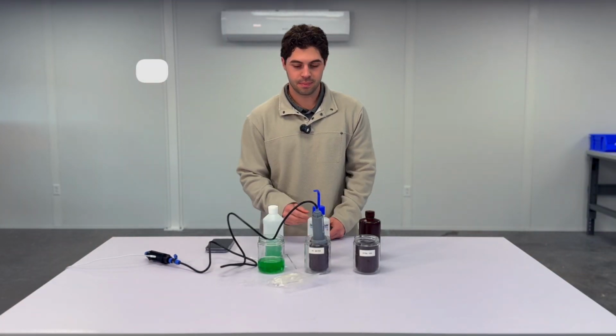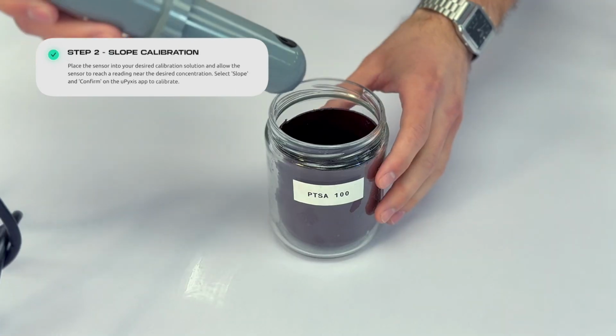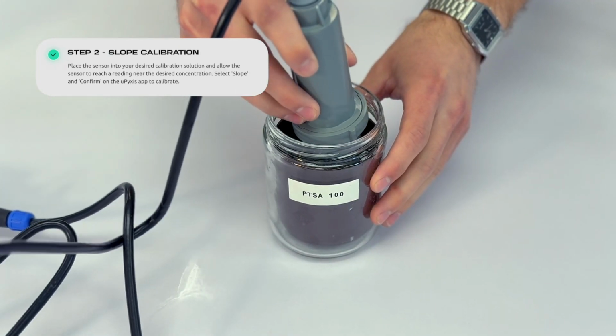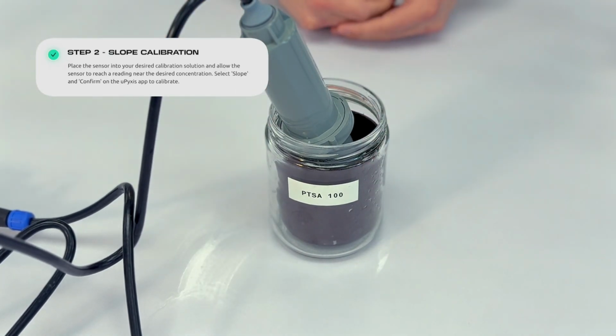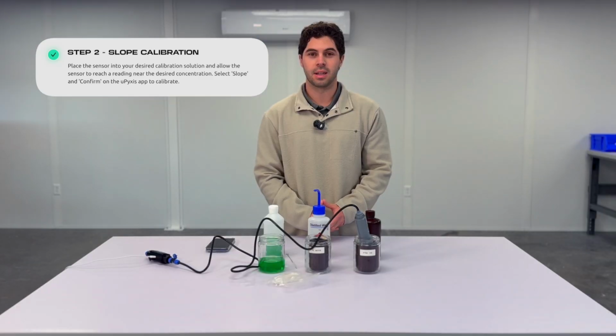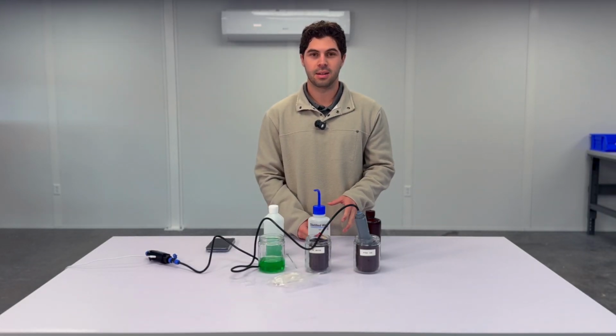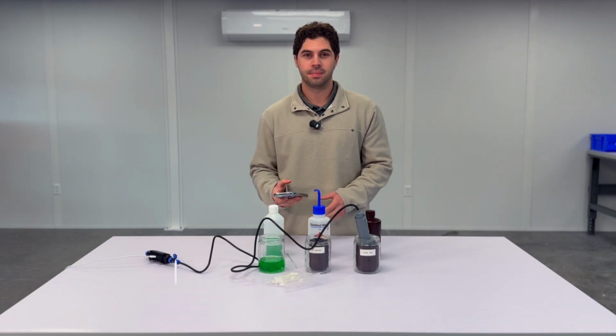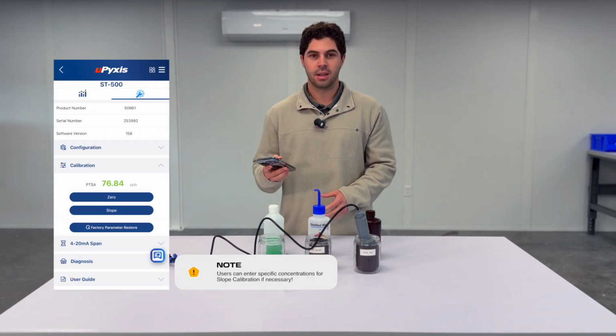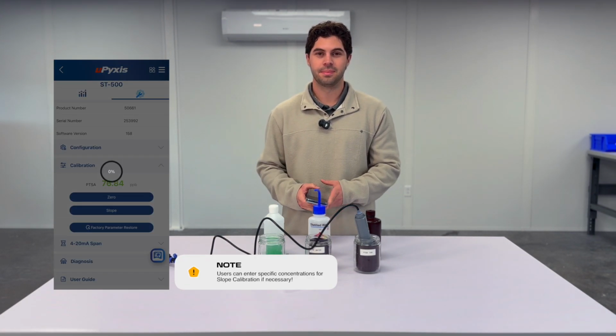Now the next step, you're going to take your probe, place it in the appropriate solution. In this case, we're using 100 ppb PTSA. Again, you're going to want to use a container that does not allow ambient light. Then you're going to head over to the Pyxis app, scroll back down to calibration, hit slope, and then confirm.